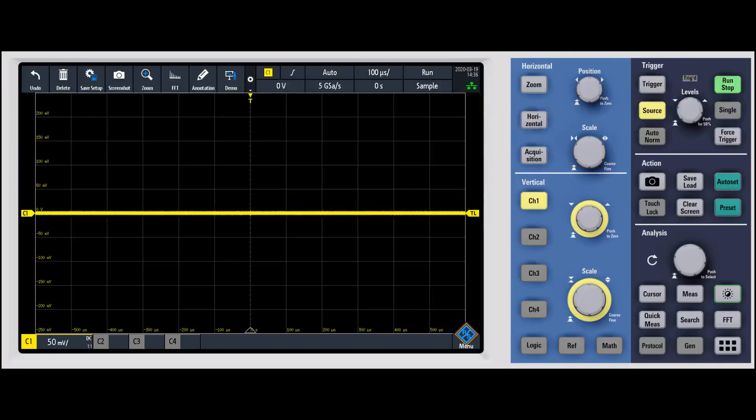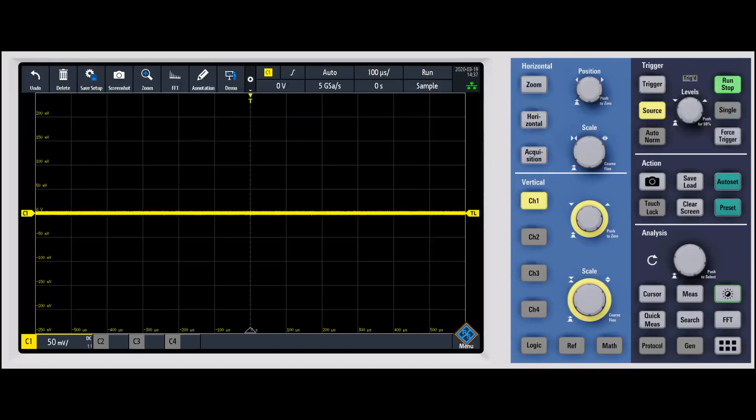I wanted to show you how to properly measure noise if you want to compare noise between different models and how to measure it on the RTM3000. One of the first things that you want to do is I typically recommend going to a small volt per division setting.